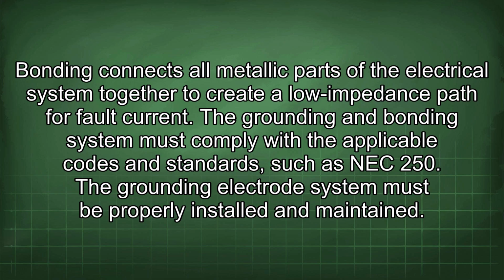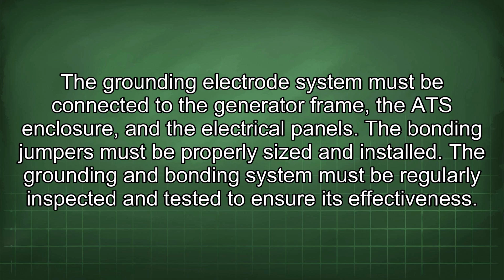The grounding electrode system must be properly installed and maintained. The grounding electrode system must be connected to the generator frame, the ATS enclosure, and the electrical panels. The bonding jumpers must be properly sized and installed. The grounding and bonding system must be regularly inspected and tested to ensure its effectiveness.